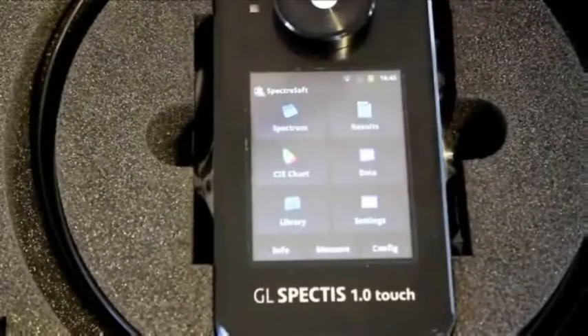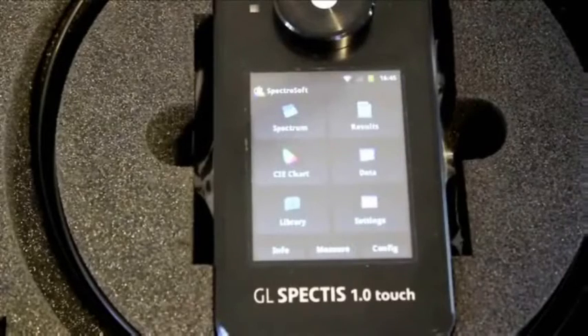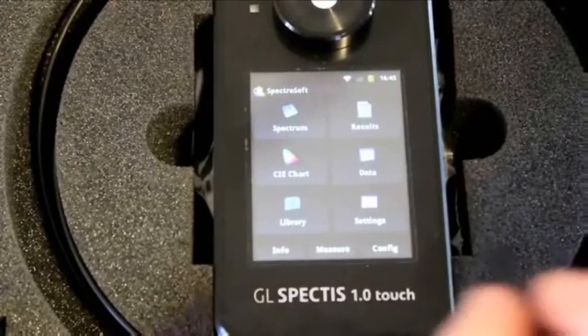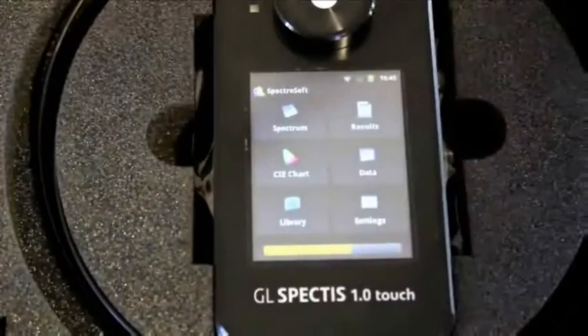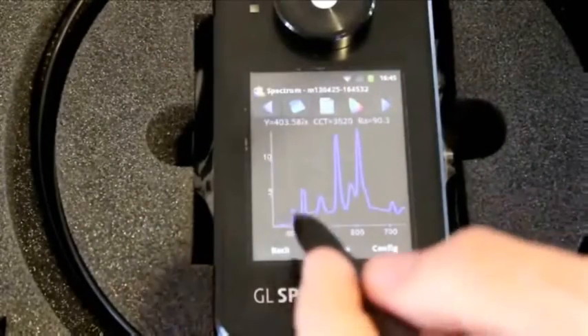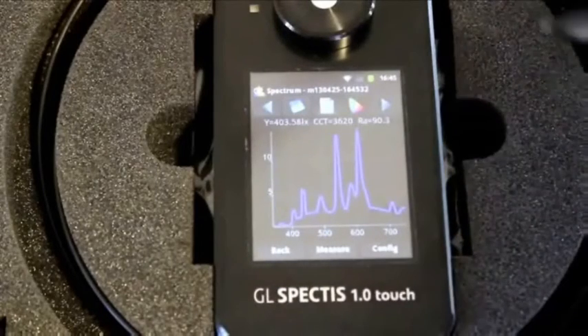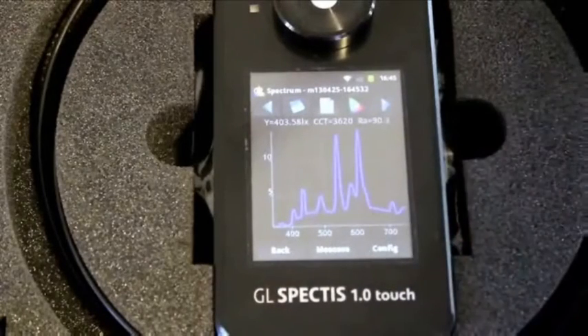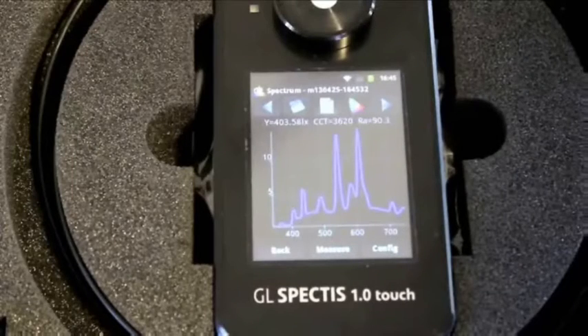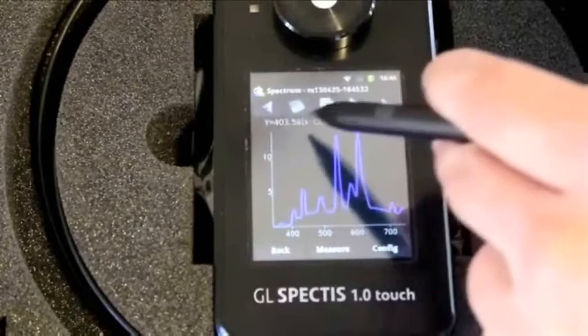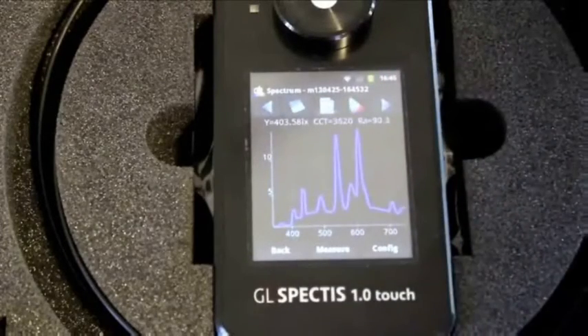So now I can take a measurement on the device. Here we have the cosine corrector measuring receptor head attached. So I'm measuring illumination in lux. So I'm simply just going to press measure here. And the spectral profile from 340 to 750 nanometres will be displayed. And we can see the two large fluorescent peaks from the lighting in this room at the moment.